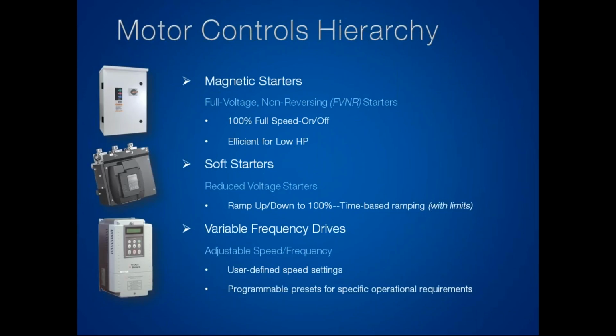All right, so first things first, let's talk about some of the different forms of motor controls that we're going to see. The first and most basic thing we're going to see is a magnetic starter, okay? This is referred to as an across-the-line starter. This is full voltage, non-reversing, 100% on, 100% off. Your starter is a light switch, okay? So we don't have a whole lot of control with the starter. It's either on or off. We're usually going to see starters on lower horsepower motors.